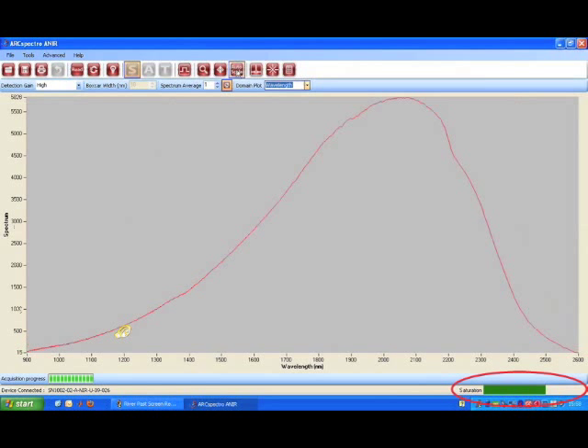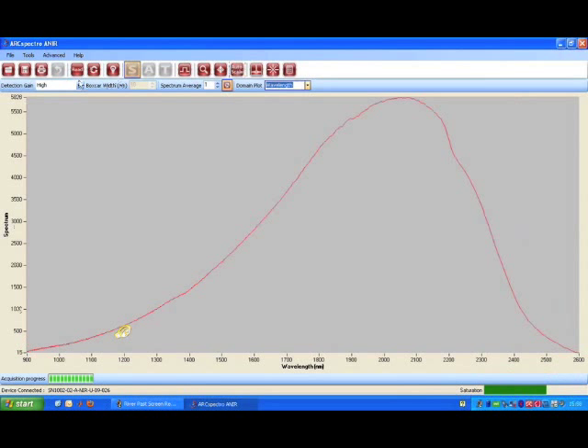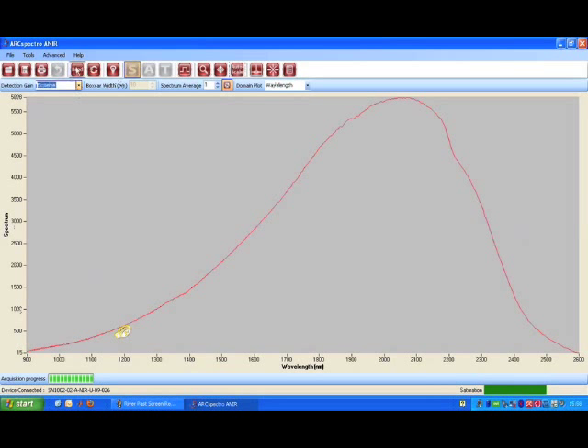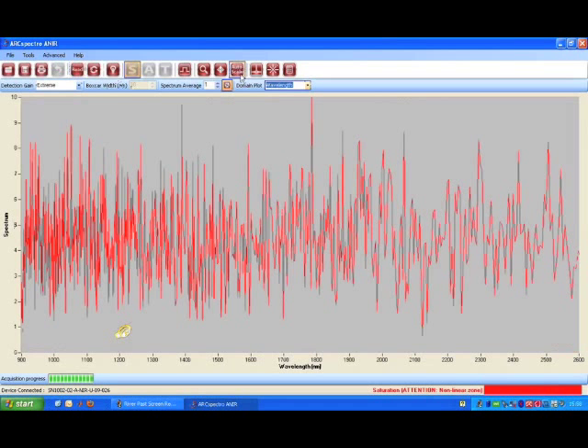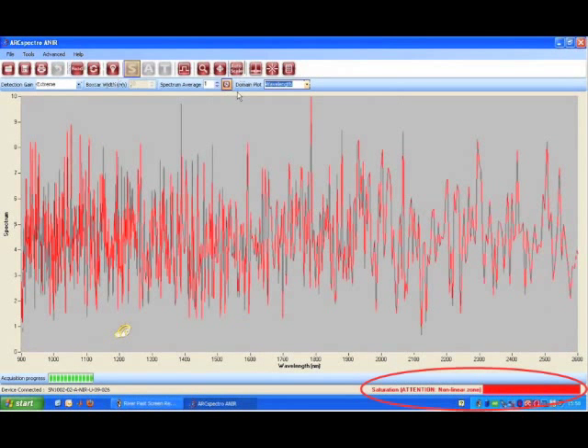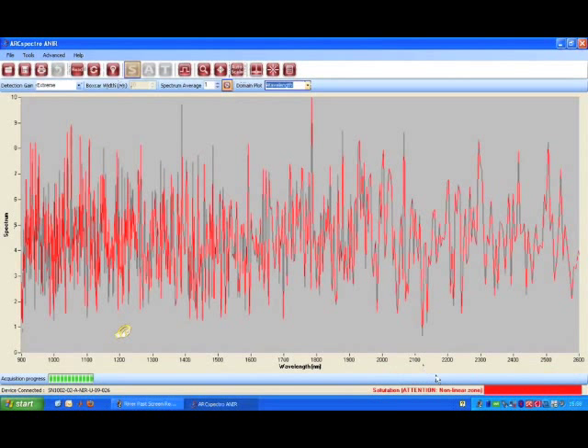As you can see on the saturation bar, the signal level on the detector is now satisfying. However, let's turn to the extreme level and take another measurement just to see what happens. The detector is now saturated and the instrument cannot show any physically significant data. Let's set back the gain to high and take a measurement again.